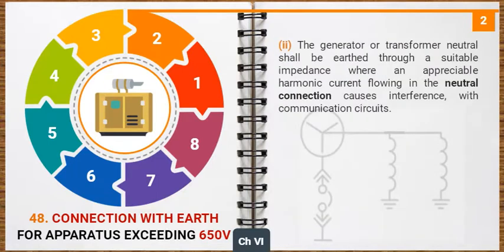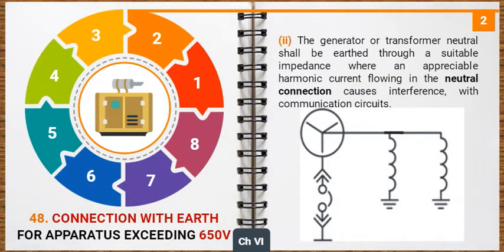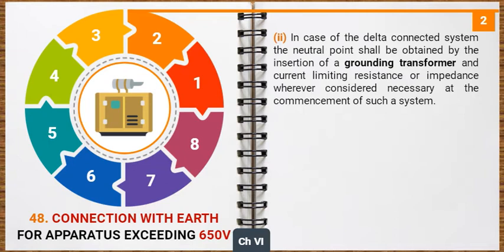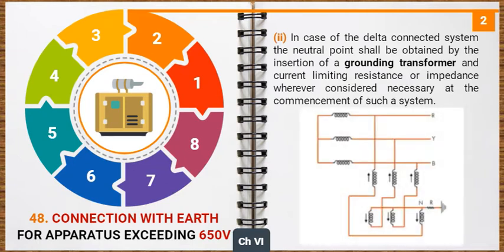The generator or transformer neutral shall be earthed through a suitable impedance where an appreciable harmonic current flowing in the neutral connection causes interference with communication circuits. In case of the delta-connected system, the neutral point shall be obtained by the insertion of a grounding transformer and current limiting resistance or impedance wherever considered necessary at the commencement of such a system.